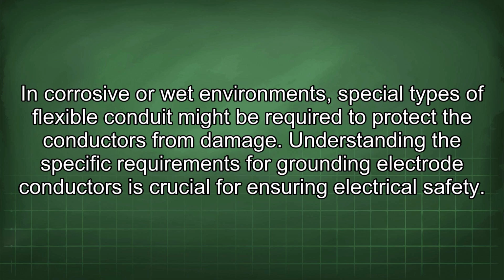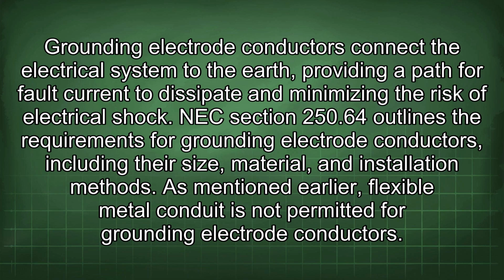Understanding the specific requirements for grounding electrode conductors is crucial for ensuring electrical safety. Grounding electrode conductors connect the electrical system to the earth, providing a path for fault current to dissipate and minimizing the risk of electrical shock. NEC Section 250.64 outlines the requirements for grounding electrode conductors, including their size, material, and installation methods.